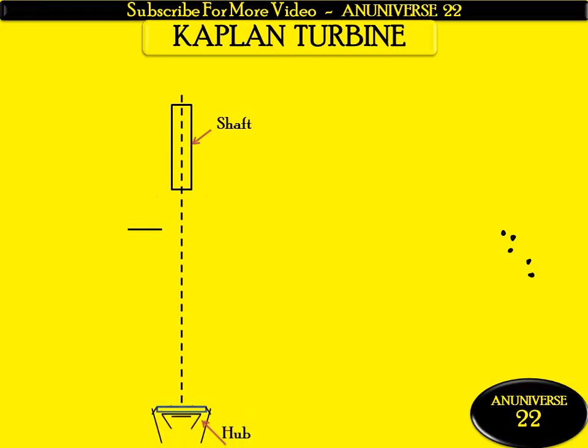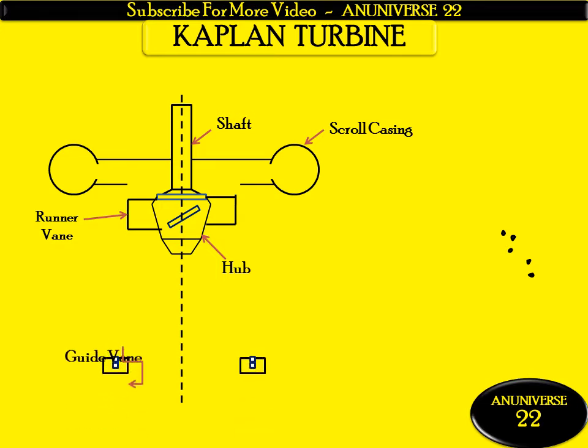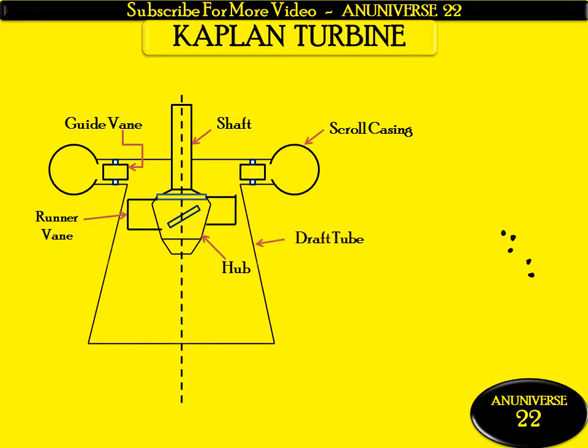This is the shaft to which the hub of the turbine is attached. This is the hub. These are the vanes on the runner, which vary from 3 to 6. This is the scroll casing — these are the main parts of the Kaplan turbine. These are the guide vanes, which guide the water from the casing towards the runner vanes. And this is the draft tube, which is used only in a reaction turbine, as in the Kaplan or Francis turbine, showing the path for water to discharge towards the tailrace.